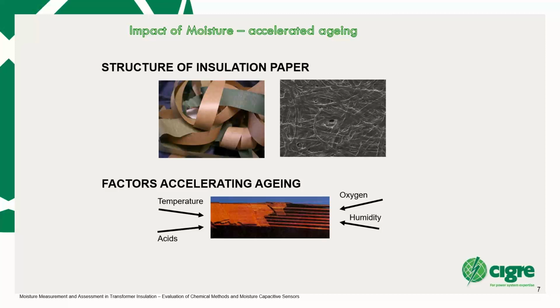Insulation paper consists of cellulose and hemicelluloses, and the hemicelluloses is something like glue which sticks everything together. When we have oxygen, that is air, which we have on earth, plus the temperature we have in a transformer, we get acids which develop out of the solid and liquid insulation, along with humidity. This leads to accelerated aging of the solid insulation.